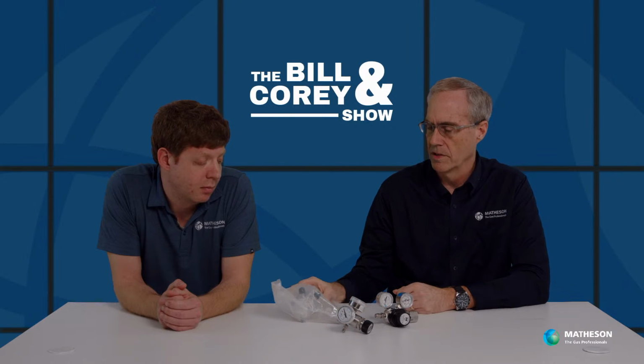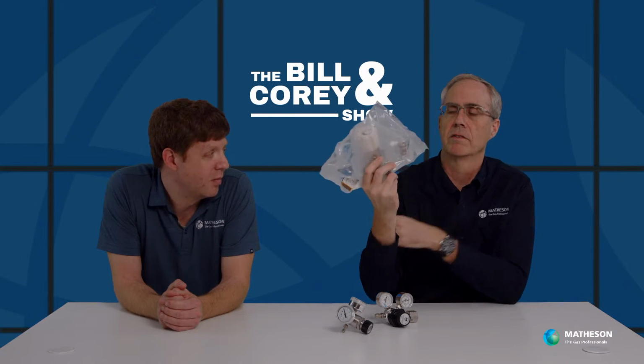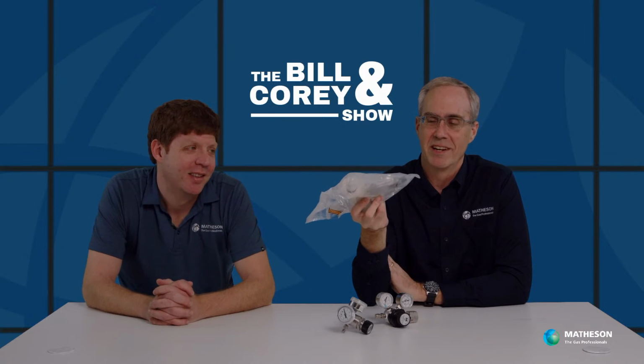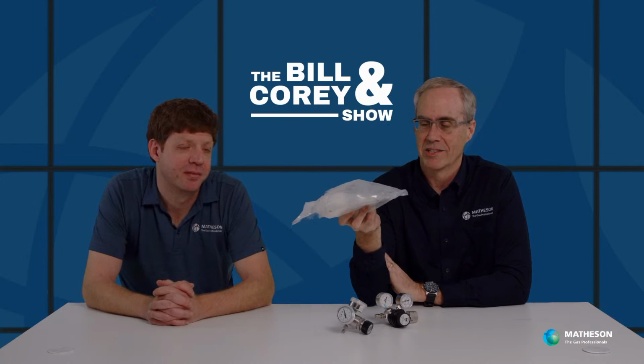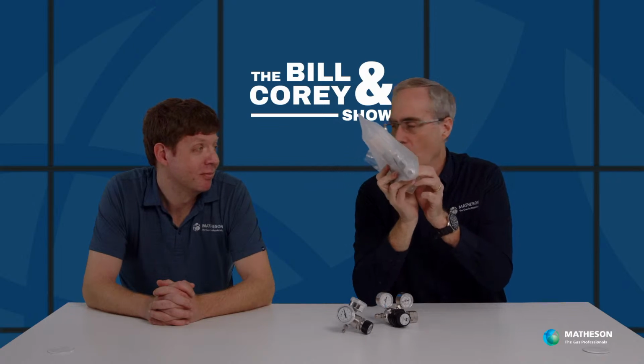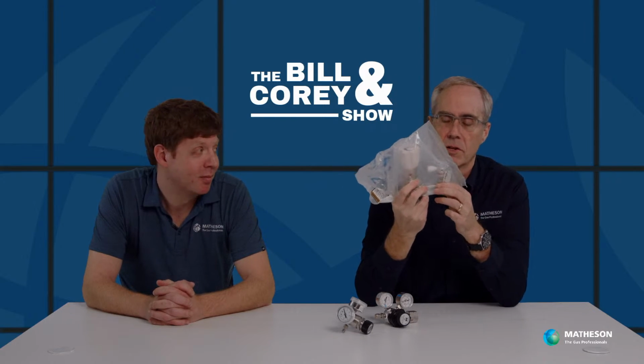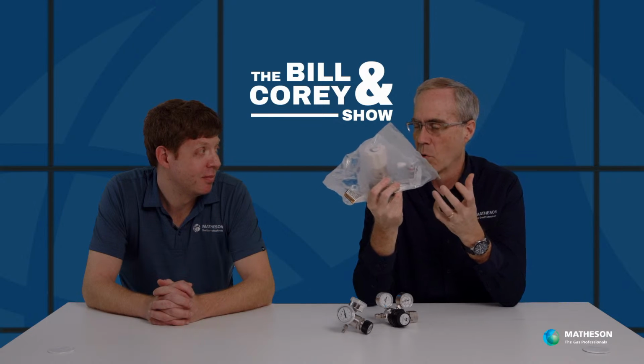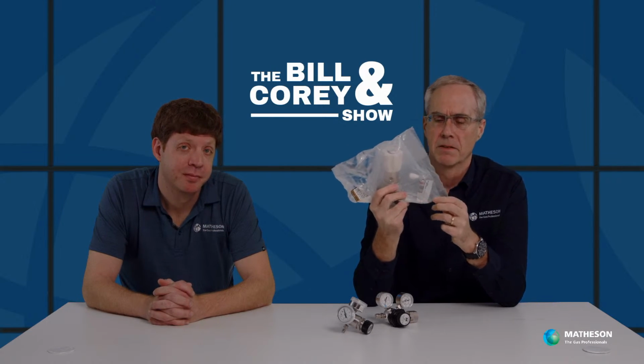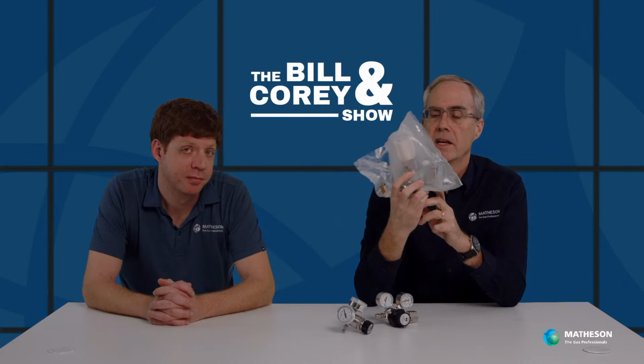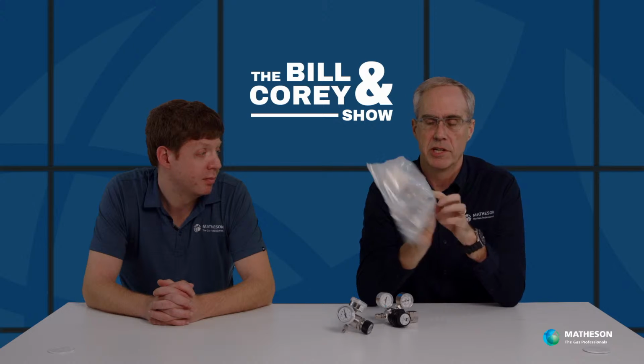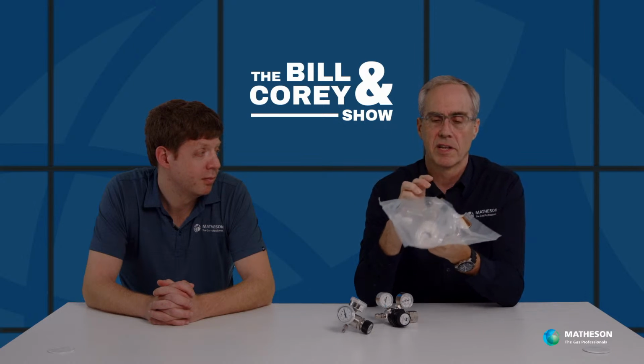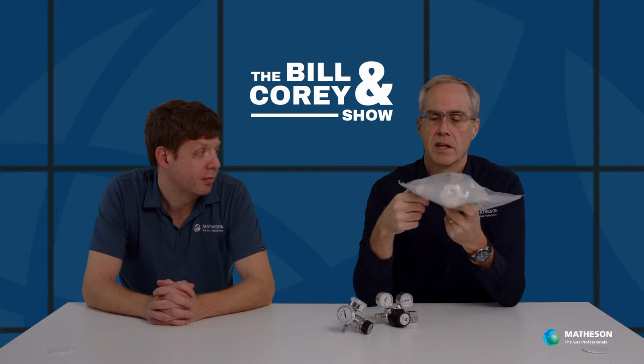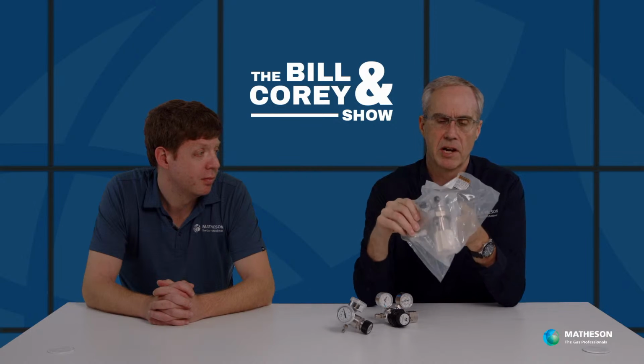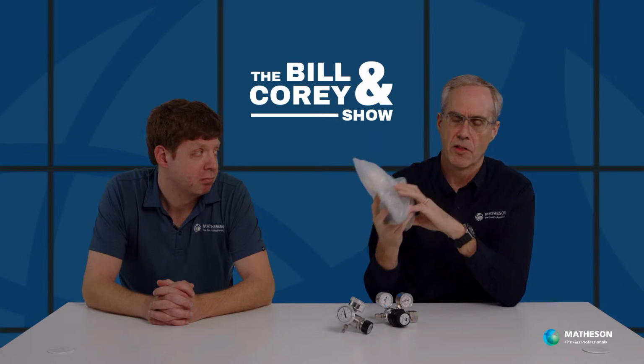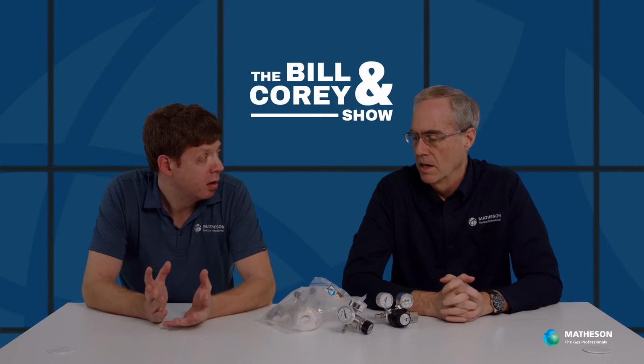We also offer this, double wrapped for freshness. This is a semiconductor grade regulator that's electro-polished. So you don't have as small of a dead volume, but it has electro-polished surfaces, so it's not as porous as regular stainless steel. So there's less chance for components to hide. It's all welded. We weld the CGA fitting on the inlet. The gauges are VCR, so you can't weld those on. An outlet valve is welded on there too, and it's got a purge port as well. So that's another possibility for VOC.